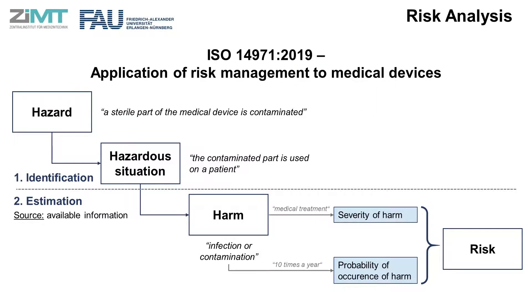Once the risk management plan is established, the step of analyzing risks can begin. The common approach starts with the identification of hazards and hazardous situations. For example, a hazard can be that a sterile part of the medical device is contaminated, which may result in the hazardous situation that the contaminated part is used on a patient. The associated harm and risk must next be estimated — in this example, the harm could be infection or contamination. The occurrence probability and severity of this harm have to be estimated with respect to the particular medical device, using available information and data, such as field data from an equivalent device. You might estimate that infection occurs approximately 10 times a year and usually requires medical treatment.